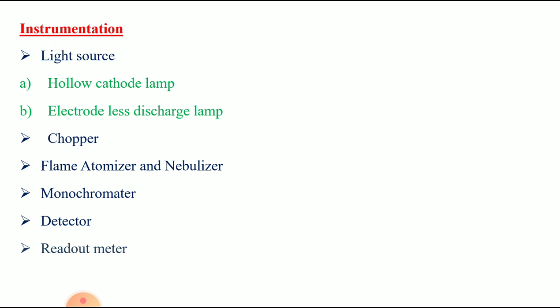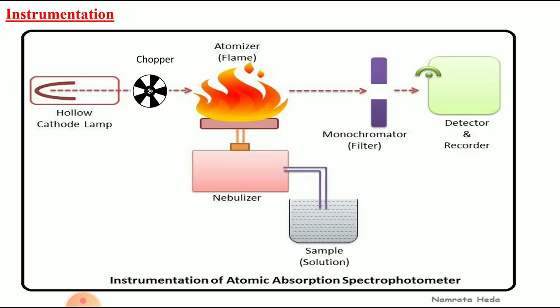In the instrumentation, there is a light source, chopper, flame atomizer and nebulizer, monochromator, detector, and readout meter. This is the schematic representation of the atomic absorption spectrophotometer. The sample in solution form goes to the nebulizer, where it is converted into fine droplets or aerosol form. These fine droplets are exposed to the flame and converted to atoms. Light from the hollow cathode lamp passes through the chopper, then reaches the flame where atoms absorb the radiation. The absorbed signal then goes to the monochromator and detector, which detects how much light is absorbed and transmitted, and the result reaches the readout device.